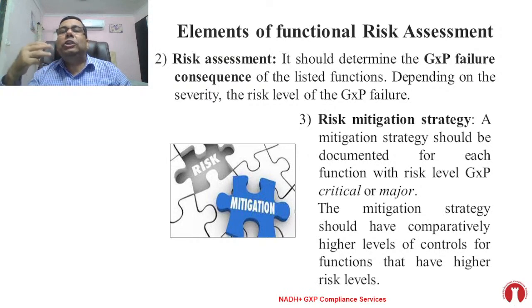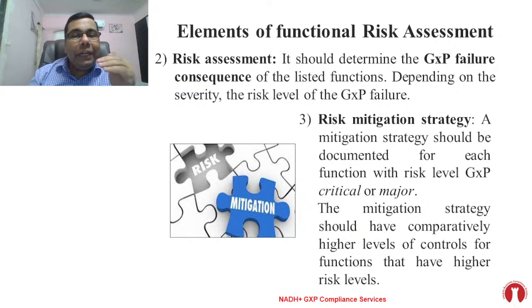The third is risk mitigation strategy. Based on the risk assessment, a mitigation strategy should be documented for each function with the risk level - GXP critical, major, or minor, whatever. Based on that, you identify how to control the risk. You cannot make the risk zero - there will always be some residual risk. But based on whether it's critical, major, or minor risk, you put a mitigation strategy in place, saying this control needs to be in my software or system so that this risk is not present in my controlling mechanism. So you have to categorize the risk as critical, major, or minor.